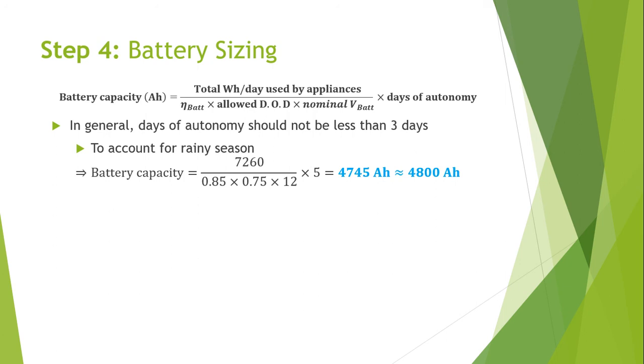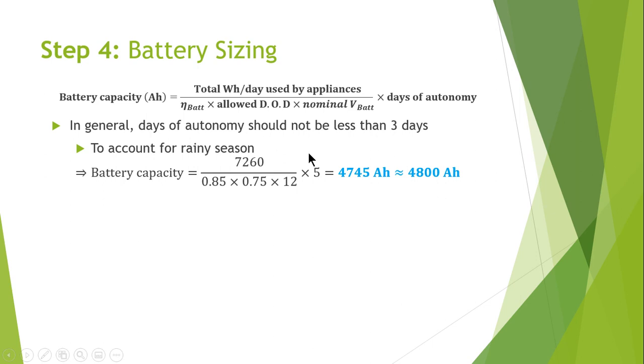The battery capacity is calculated using 7,260 watt-hours per day, battery efficiency of 0.85, DOD of 0.75, battery voltage of 12 volts, and days of autonomy of 5 days.